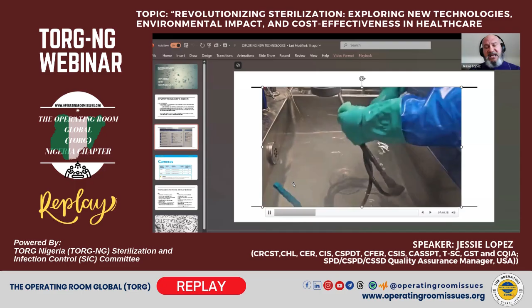And as you can see, the cord, even though it was neatly coiled under there, can coil up on itself. And as you're wiping, you want to transfer this over to the next step in the cleaning process, and that would be to rinse, flush, and brush the device, according to the IFU. Doing this removes some of the loose soils, and you're observing and inspecting it as you transfer it over. Now, bear with me as I move my camera over so that I can show you the next step in the process.